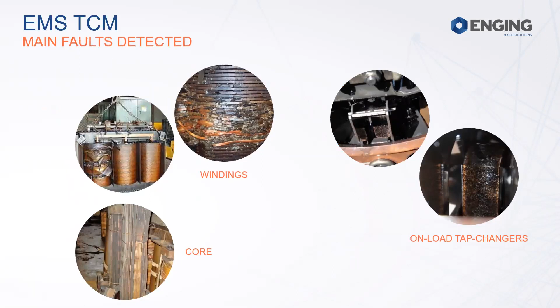Basically, as you can see from the photo, the on-load tap changer is completely carbonized at this moment. It should be copper with a copper color and is completely carbonized. So basically, we are able to detect not only the electrical faults that happen in the core and windings, but we are reaching also a more mechanical fault detection in the on-load tap changer.